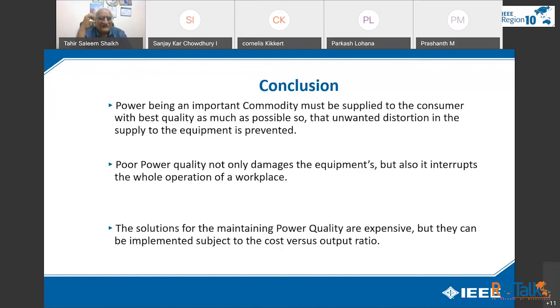So whenever you install a UPS for this type of harmonic distortion, you should have a built-in filter or install a separate filter of whatever type may be required. And proper earthing, as I have said, is TN-S, meaning the neutral and ground cable should be run separately across the whole distribution system.